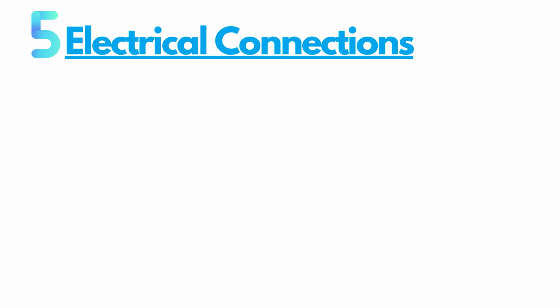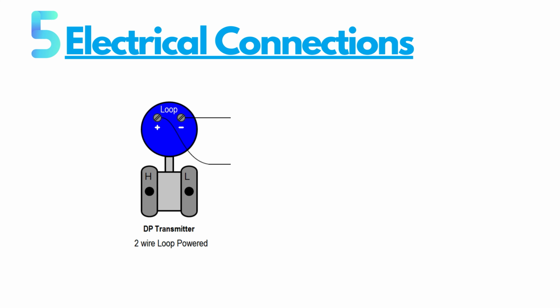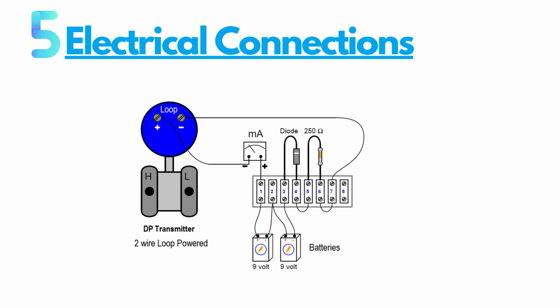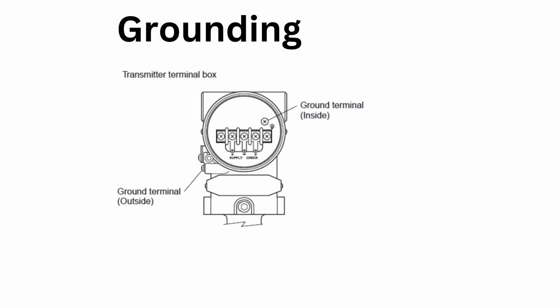Step 5. Electrical connections. Next, make the electrical connections according to the manufacturer's instructions. Connect the transmitter as 2-wire loop powered. Grounding is always required for the proper operation of transmitters.